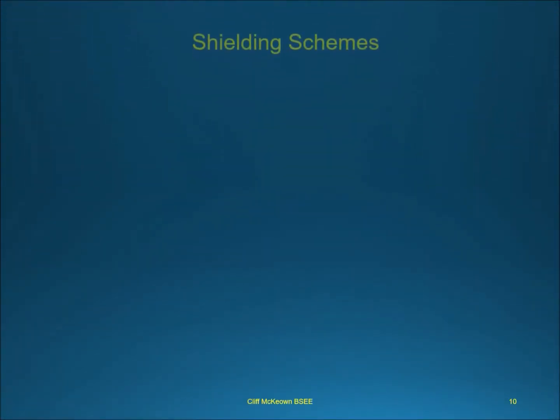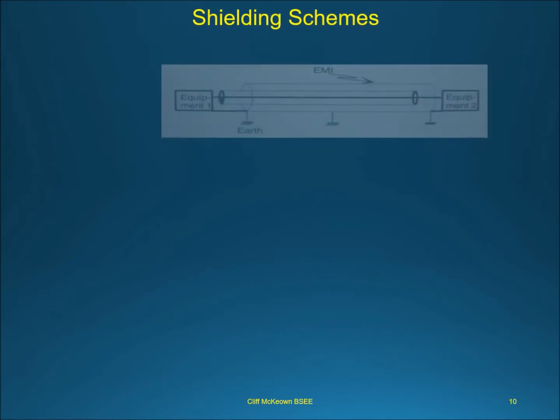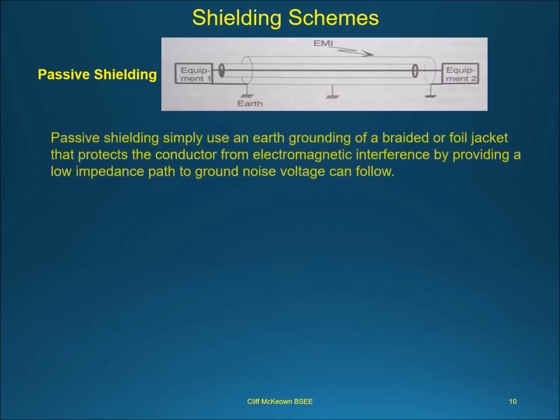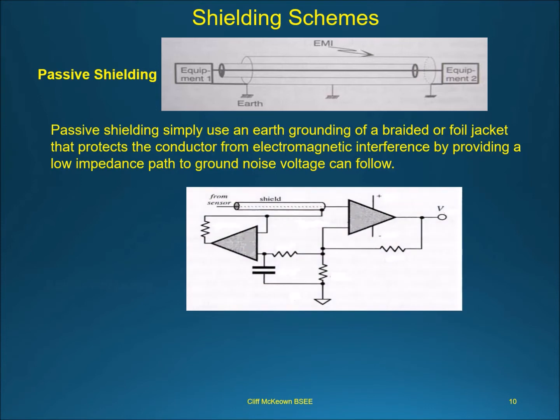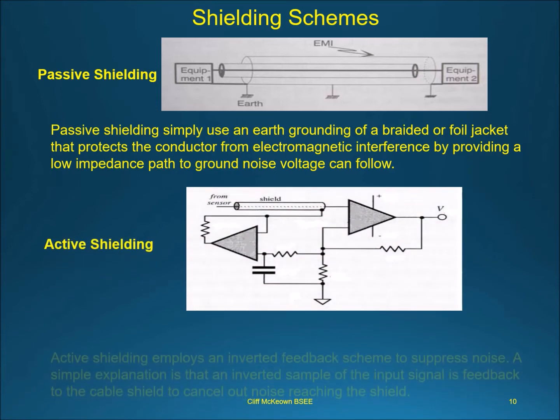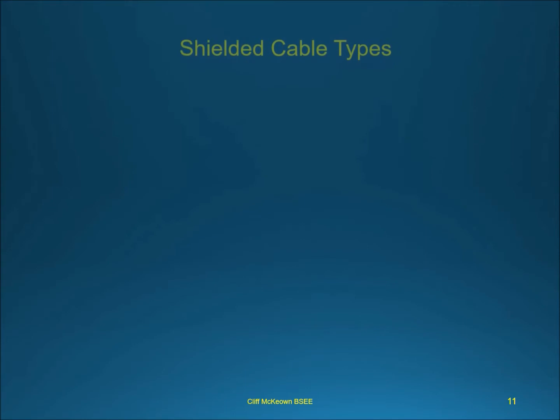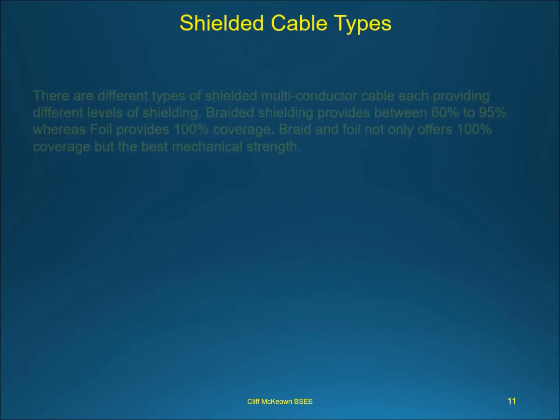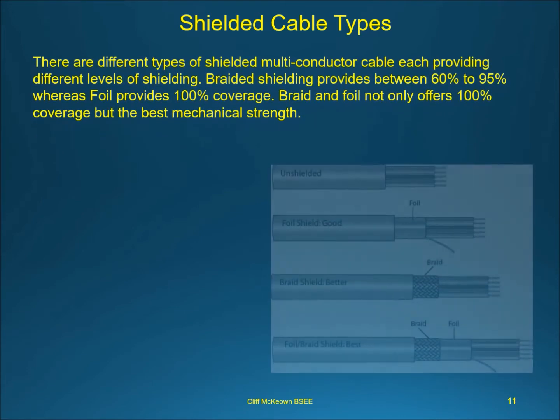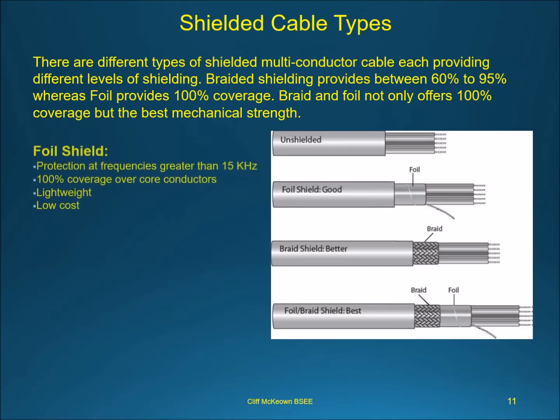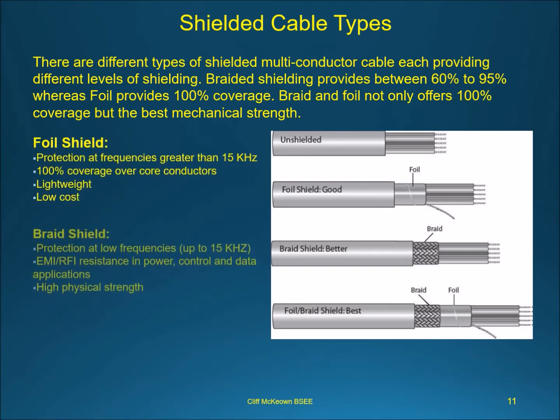Shielding schemes. Passive shielding simply uses an earth grounding of a braided or foil jacket that protects the conductor from electromagnetic interference by providing a low impedance path to ground that noise voltage can follow. Active shielding employs an inverted feedback scheme to suppress noise — an inverted sample of the input signal is fed back to the cable shield to cancel out noise reaching the shield. There are different types of shielded multi-conductor cables, each providing different levels of shielding. Braided shielding provides between 60% to 95% coverage, whereas foil provides 100% coverage. Braid and foil combined not only offers 100% coverage but the best mechanical strength.